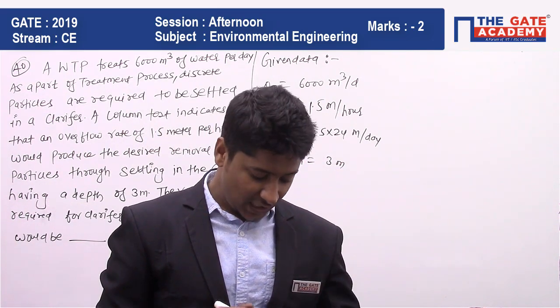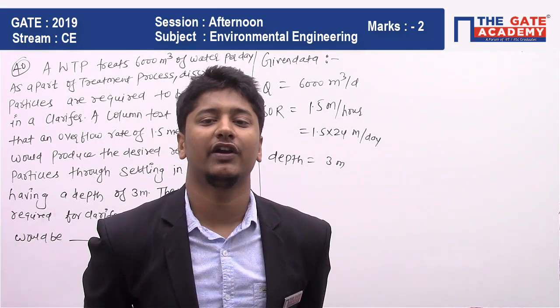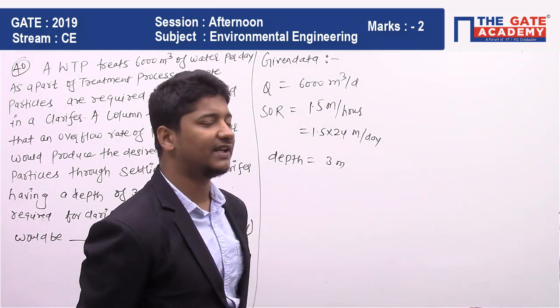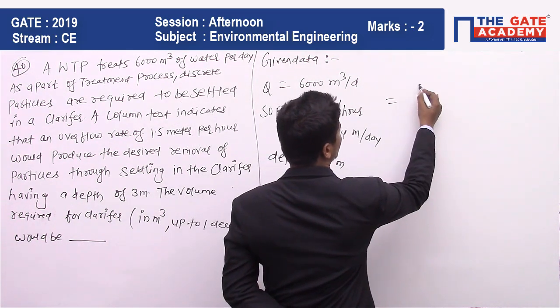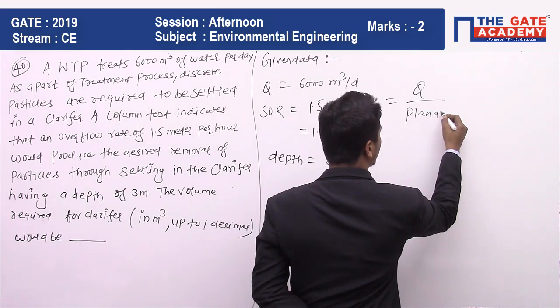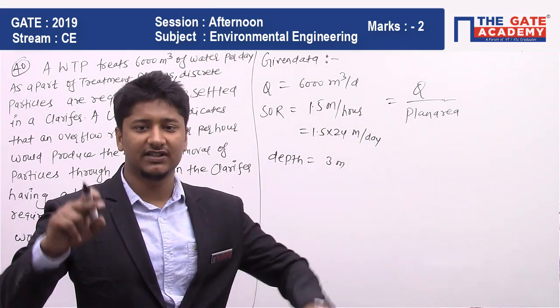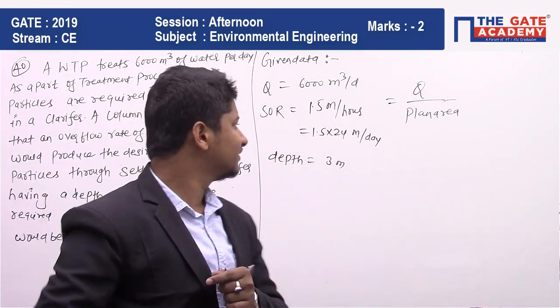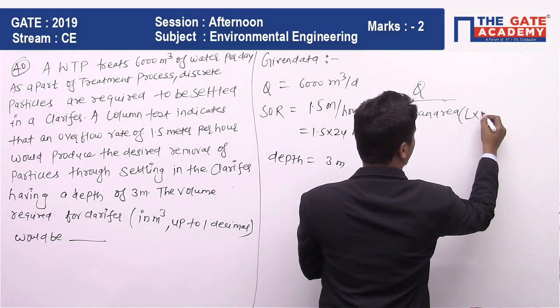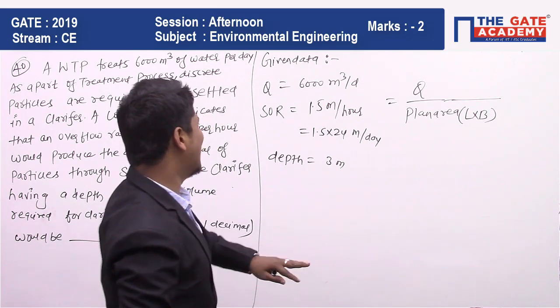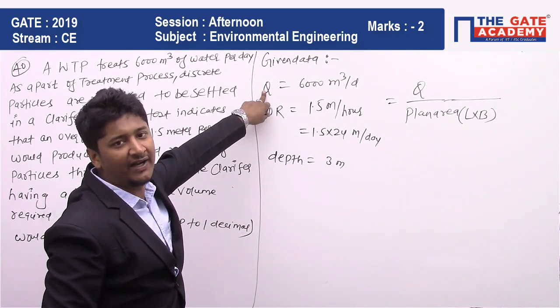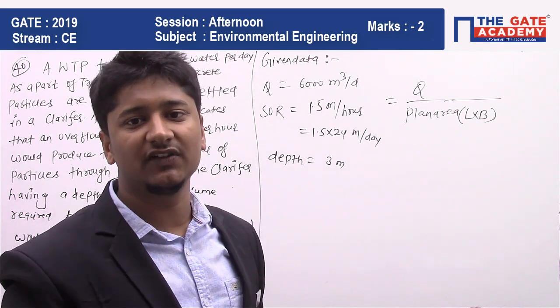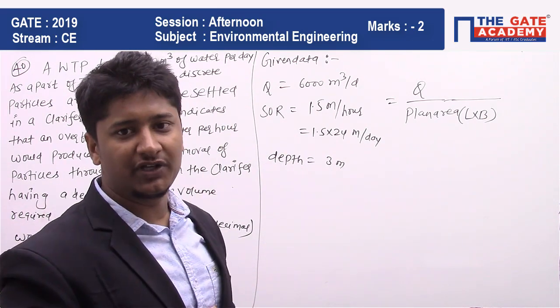Surface overflow rate is nothing but discharge upon plan area of the clarifier. If you look at the clarifier, it has a height, a length, and a width. The plan area is the top area, that is L × B. So you have SOR and you have Q, and by using this you can find the plan area. If you have the plan area and the depth, you can easily find the volume of the clarifier. That is the approach we are going to use.